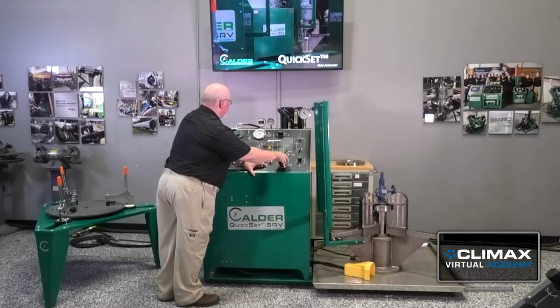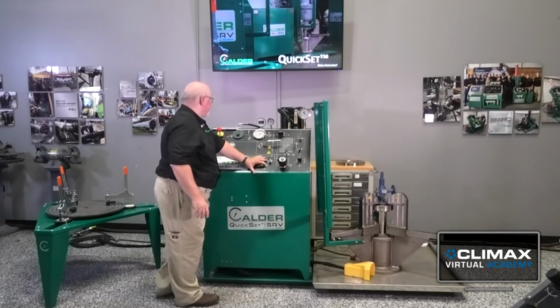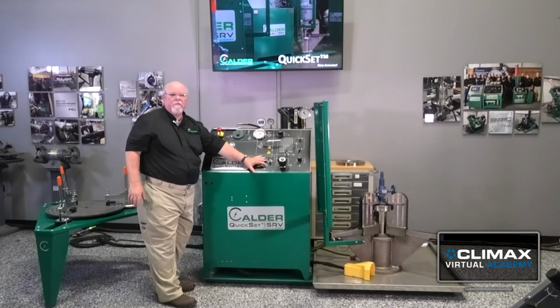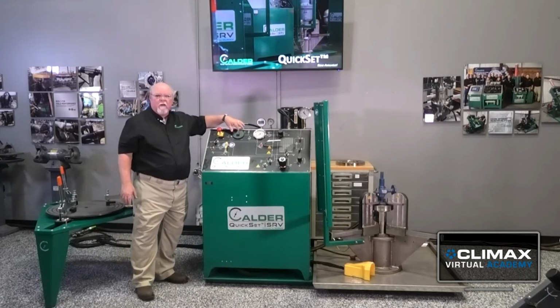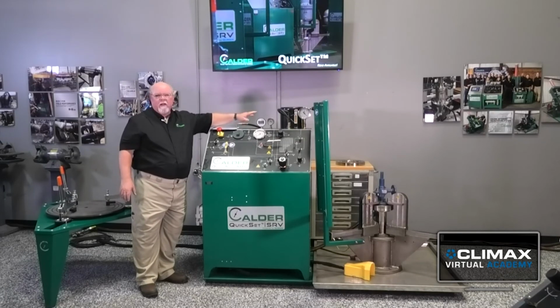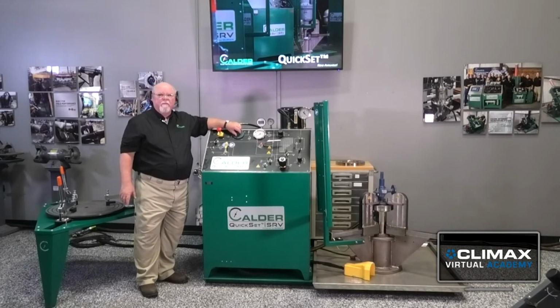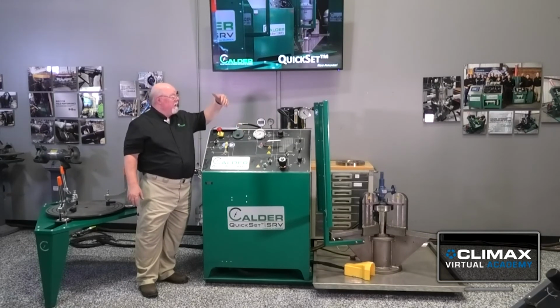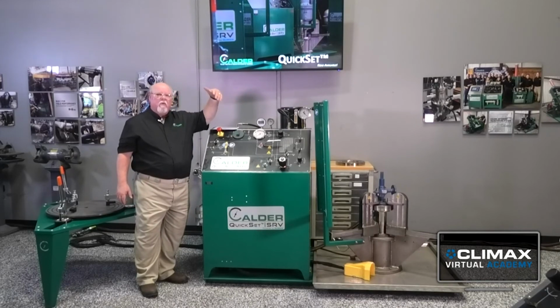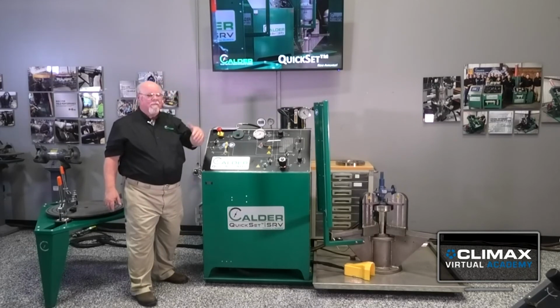But when I engage and start to build pressure, as soon as I get to a minimal amount of pressure, in this case 15 psi, the interlock is engaged. I don't know if you can see that, but there's 15 psi on the system. So it's a minimal amount of pressure to engage the test stand. The test light is not on yet. It will go on around 50 psi to indicate that the pressure is even higher.